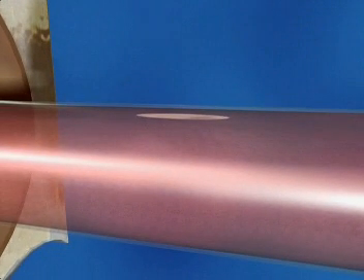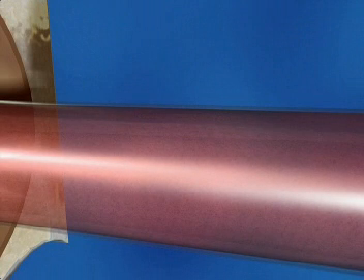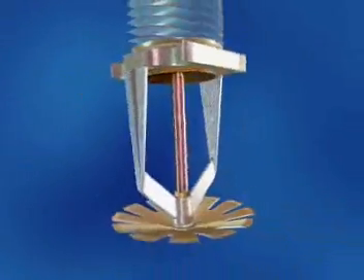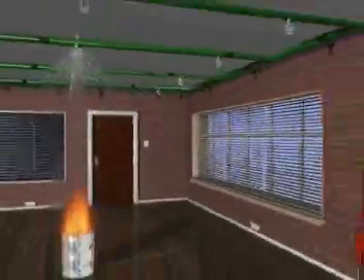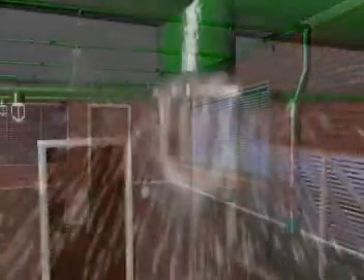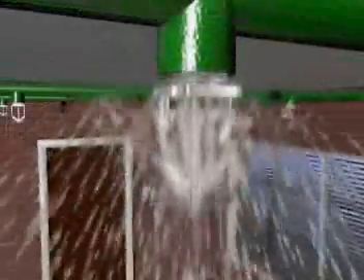When the liquid expands under the influence of heat from a fire, pressure in the bulb rises until the vapor is compressed. Further increases in temperature cause a rapid buildup of pressure sufficient to shatter the bulb, releasing the valve seal and allowing the water to flow onto a water distribution system.